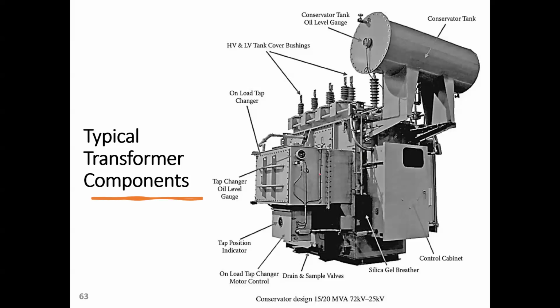So for instance, guys, we have here in this chamber what's called an on-load tap changer. The tap changer, we mentioned that you can have different voltage levels. So the tap changer is used to have variable voltage from our transformer. This is the function of using a tap. The tap is nothing but like a rheostat, which slides and moves on the winding to provide different voltage levels. So this is the function of the tap changer.